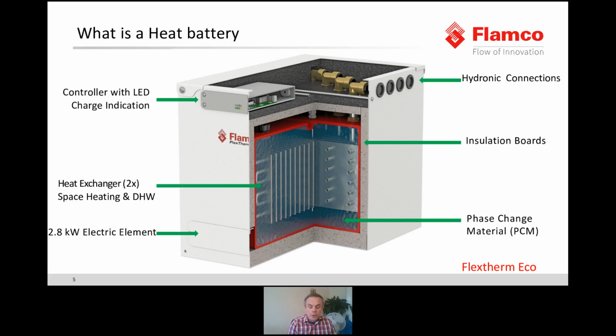So the heat battery provides hot water and central heating to a dwelling and can be provided in multiple battery configurations. The heat battery charging demand controller continually monitors the central heating, hot water and heat battery temperatures, and uses this information to calculate the charge state of the heat battery itself. If the charge state drops below a predetermined level, then the internal heating element is switched on. When the heat battery reaches its predetermined level, the heating element is switched off.